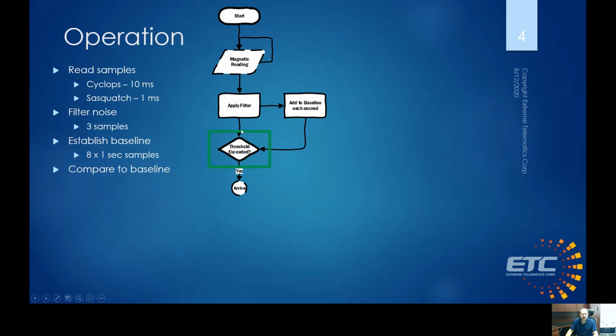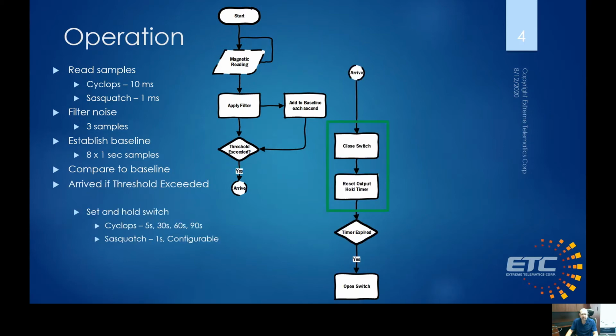Then at the same time, these filtered samples are also compared to the baseline. So once we have a baseline established, we're using that on every single filtered sample to determine if we've exceeded the threshold. And this threshold is set by the switch setting. So the different sensitivity levels give us a different amount of signal change that we have to see in order to say that the plunger has arrived.